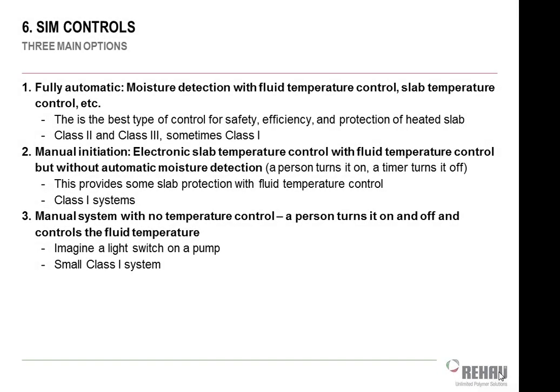Okay. So now we're back to Snowmelt Controls. So the three main choices of controls. The simplest one is number 3 down here. It's a manual system with no temperature control. It's basically a light switch on the wall. You're at your house. You see it start snowing. You turn on the switch, which kicks on your pump, which starts pulling water out of your hydronic loop for your house and sending water out to the heat exchanger for your snowmelt system.